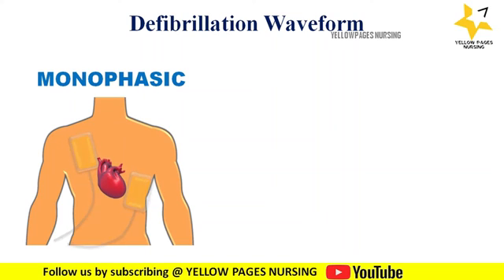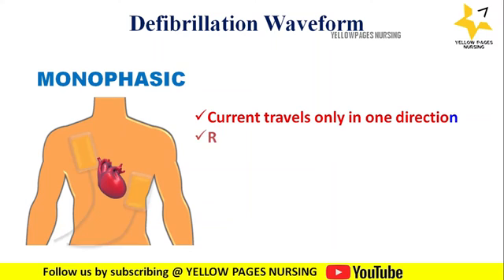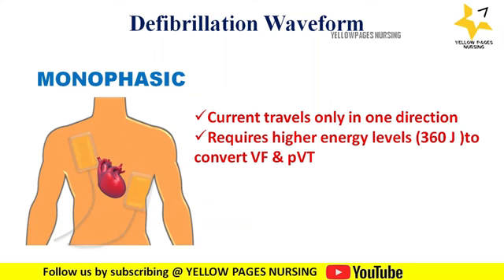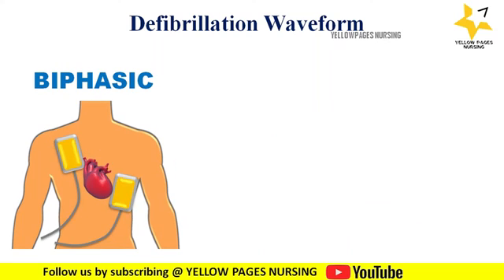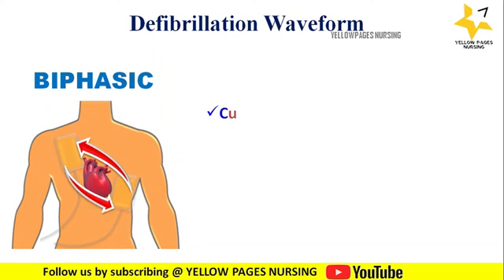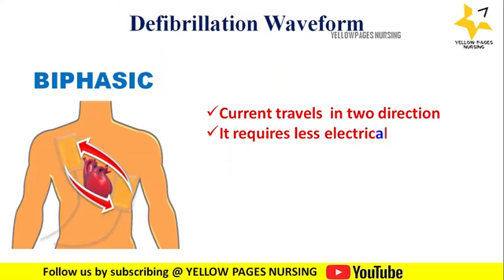Defibrillation waveforms: The first is monophasic, where current travels only in one direction and requires more energy — up to 360 joules — to convert ventricular fibrillation and pulseless ventricular tachycardia to normal sinus rhythm. The second is biphasic, where current travels in two directions, requiring less electrical energy.